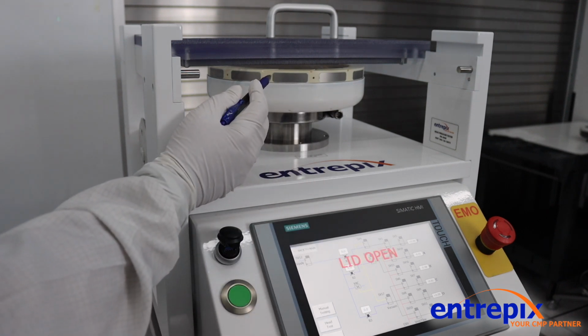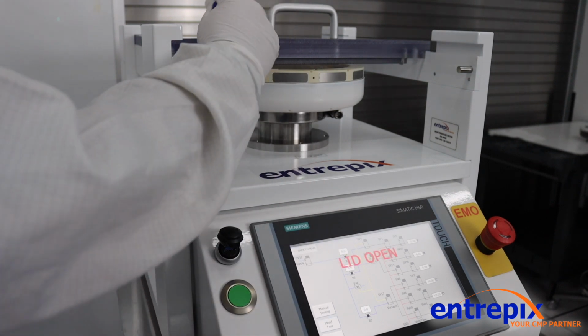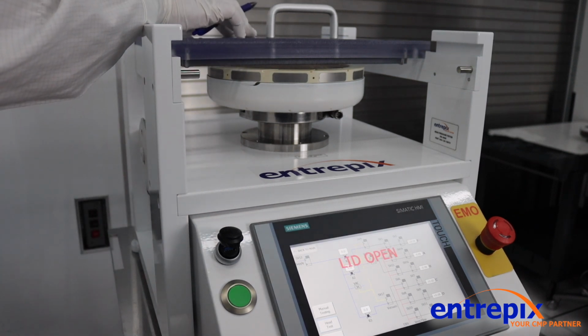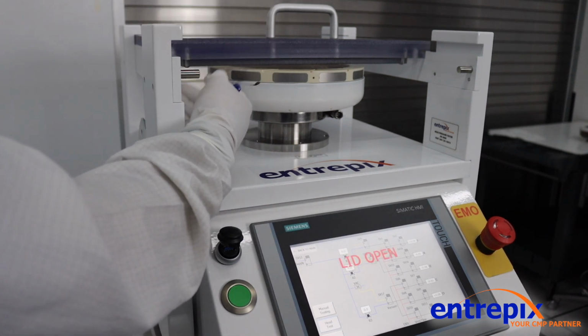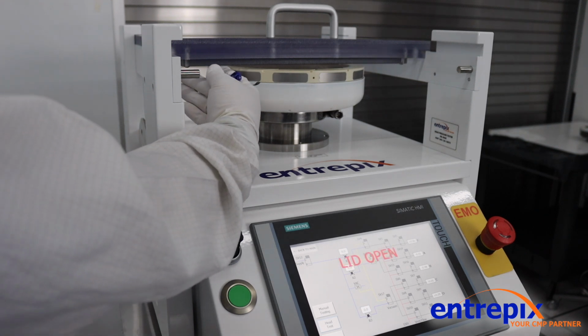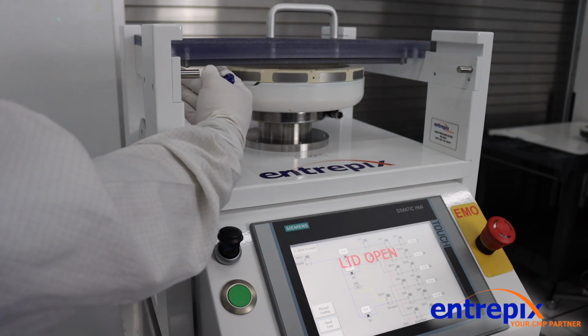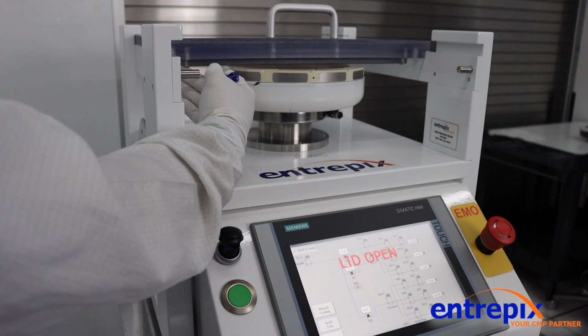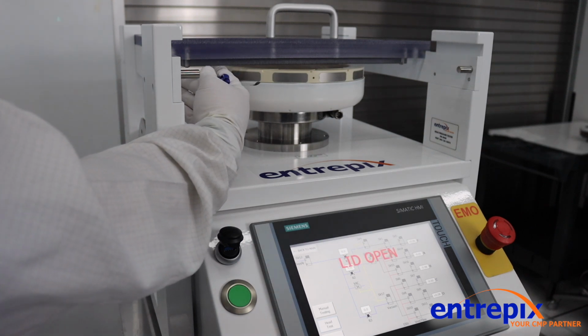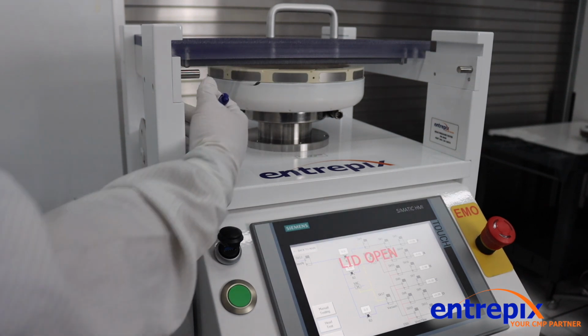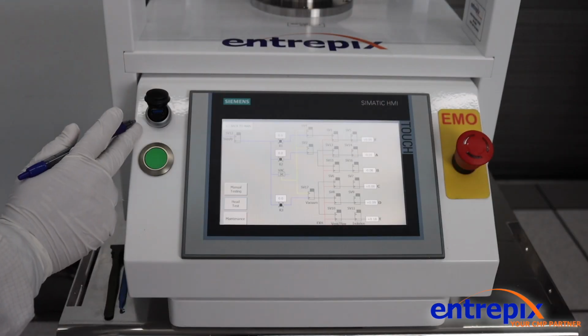Looking closer at the lid, you will notice that it's transparent, allowing you to view the testing sequence in real time. The lid is divided into two layers. The bottom layer is removable for use in testing the 300 millimeter polishing heads to accommodate the extra expansion requirements during the zone inflations. Moving on to the front, starting at the upper left is the USB thumb drive connection.